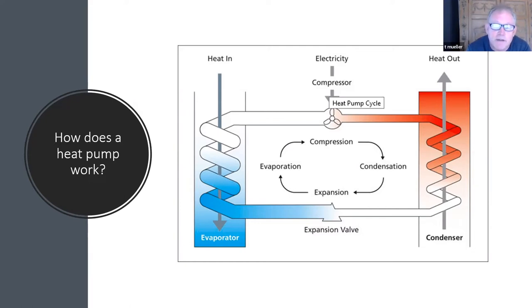Commercial systems will reuse that residual excess heat. Residential systems typically don't, but that refrigerant gets so hot that it's passed through a coil on the inside of the building in this heating cycle, and air is passed over that coil, and that heat is transferred into the air and used, and the slightly cooler refrigerant as a liquid reaches the expansion valve.